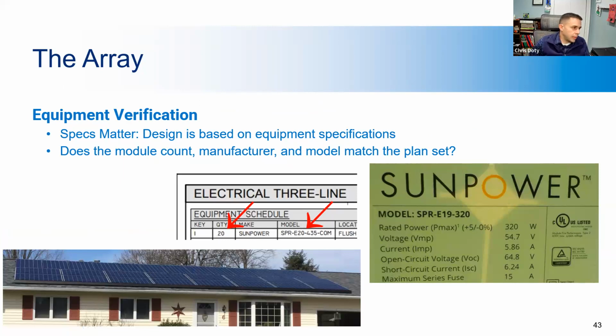So at the array, one of the main things that you want to look for is you want to compare the electrical diagram provided by the contractor and the nameplate information for the actual panels that are on site. You want to make sure that they're identical. As in this example, you can see on the electrical diagram, they have a different model number than was actually installed at the site.